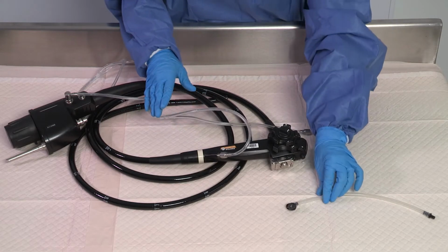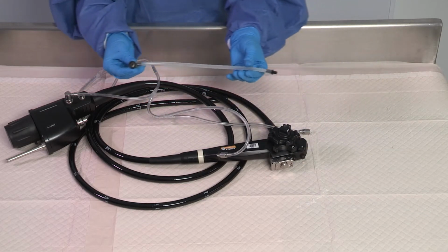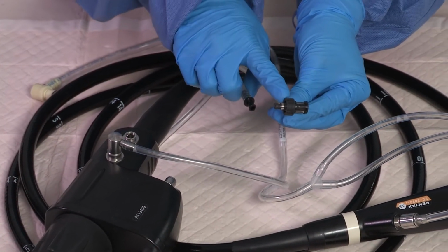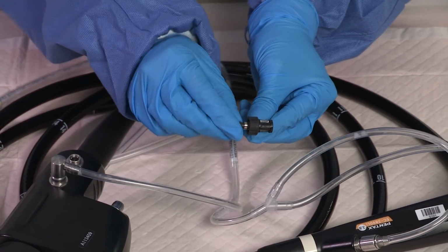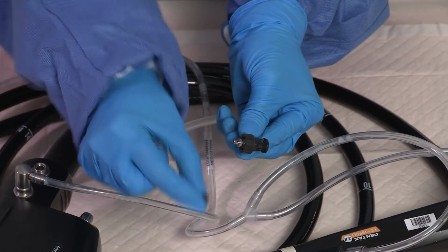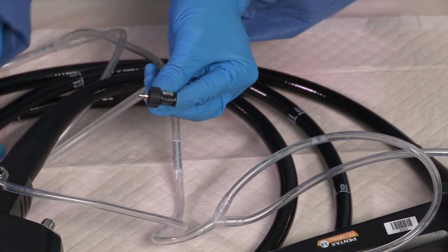For the forward water jet channel, attach the required Pentax cleaning adapters to the endoscope per the IFU. The check valve must be removed from the Pentax cleaning adapter to ensure proper flow and high-level disinfection of the channels.